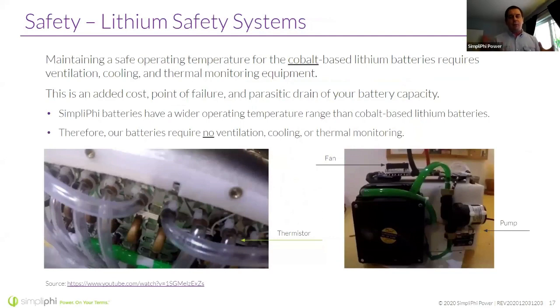When dealing with a battery that has a propensity for higher energy release or higher flammability risk, you may need additional equipment. This slide outlines that for cobalt-based batteries, they may need ventilation, cooling, monitoring equipment - in addition to a way to measure temperature, they may need the ability to circulate a coolant and have a fan to keep that coolant cold. All of these are moving parts and additional drains on the battery's energy.